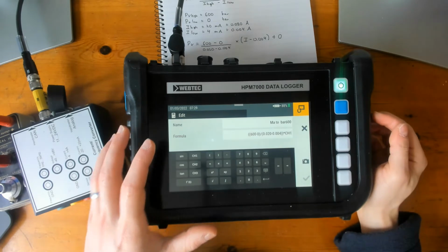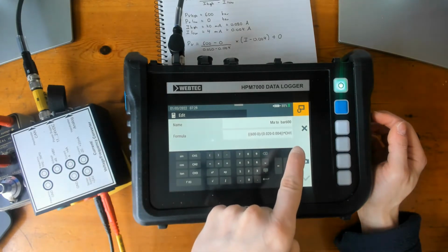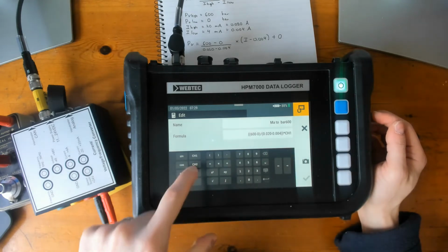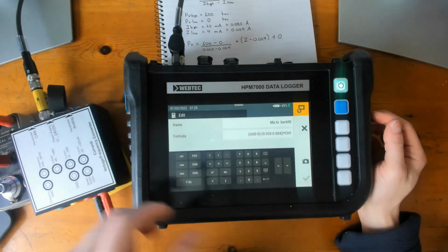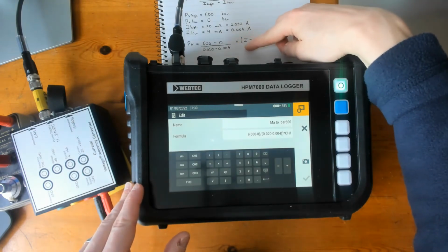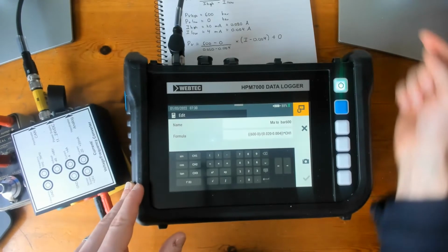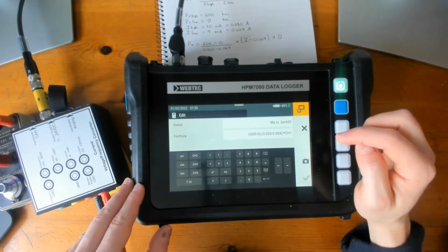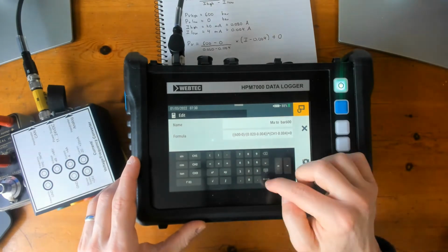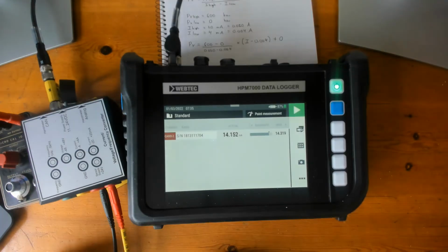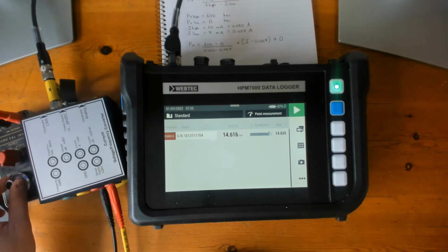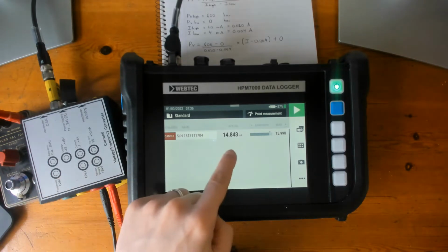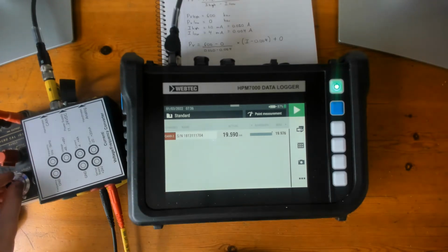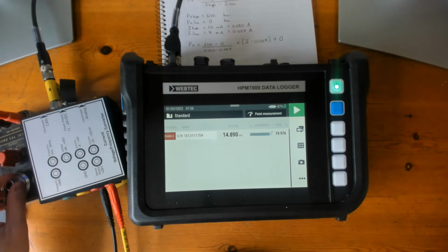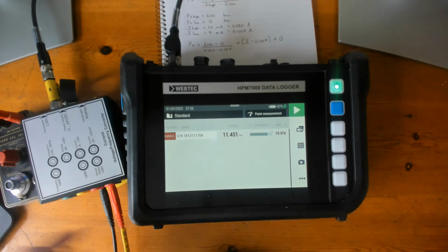So here we select the channel that we will use to get the readings. In this case, it will be channel 1. So we select channel 1, and that corresponds to this, which will be the current milliamp readings. As you can see here, I'm injecting a milliamp signal with this simulator, and the converter box will only give me the readings in milliamp. But I don't want that. I'm pretending that this is a 600 bar transducer and I want to read 600 bars on the screen.